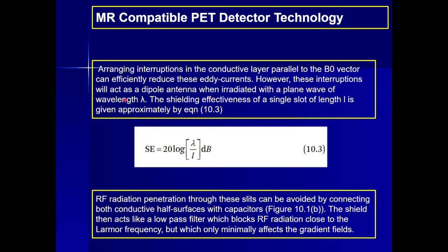However, these interruptions will act as a dipole antenna when interacting with a plane wave of wavelength lambda. The shielding effectiveness of a single slot of length L is given approximately by SE = 20 log (lambda divided by L) in decibels. RF radiation penetration through these slits can be avoided by connecting both conductive half surfaces with capacitors. The shield then acts as a low pass filter which blocks RF radiation close to the Larmor frequency but which only minimally affects the gradient fields.